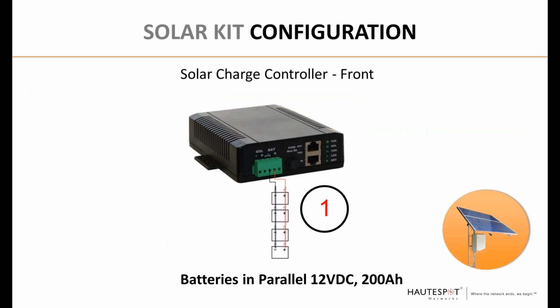So for configuration and installation, you must make sure to connect the batteries to the solar charge controller first. Connect them with the appropriate polarity, of course. Even though we do have reverse polarity protection, you want to get it right and not rely on that reverse polarity protection. So from the batteries to the PoE charge controller, the terminal labeled BAT is where you install the batteries.